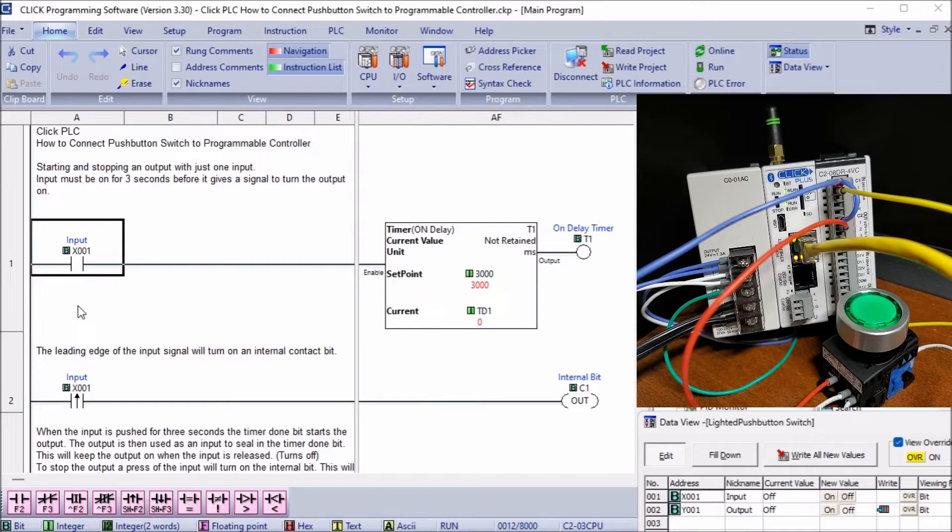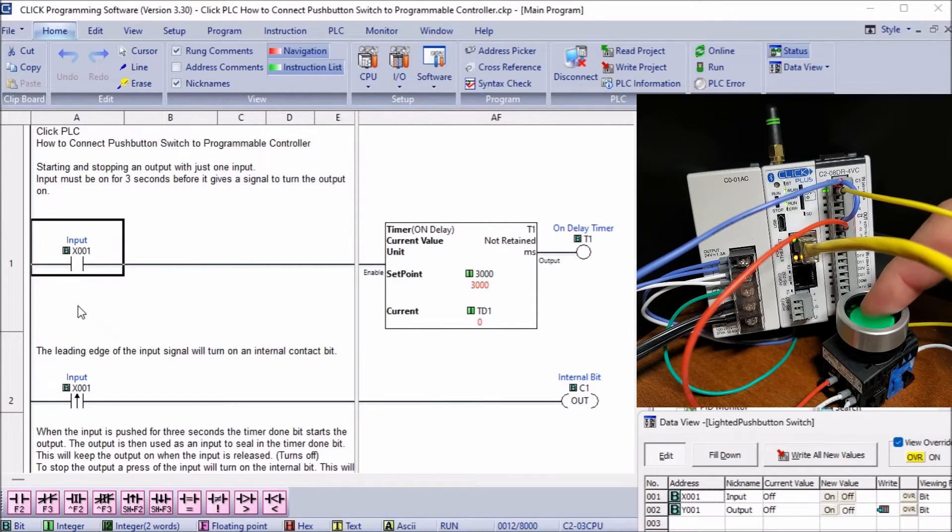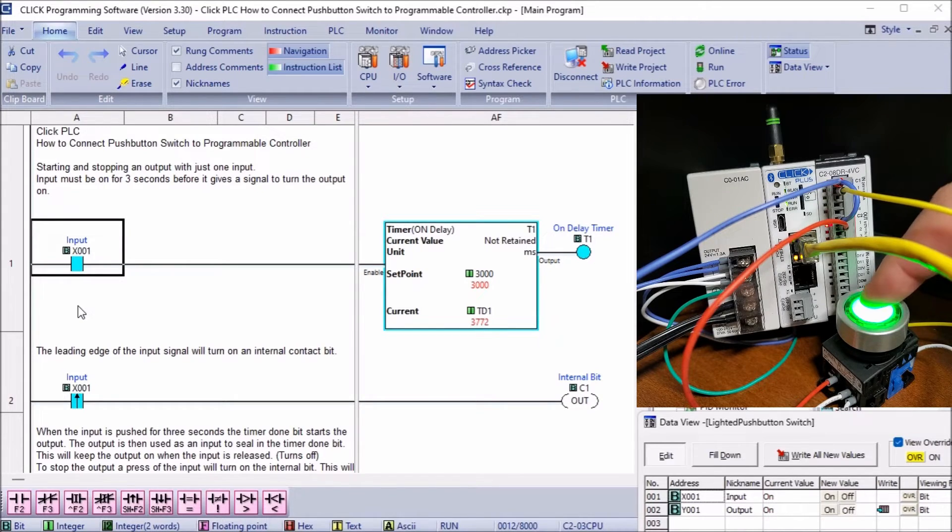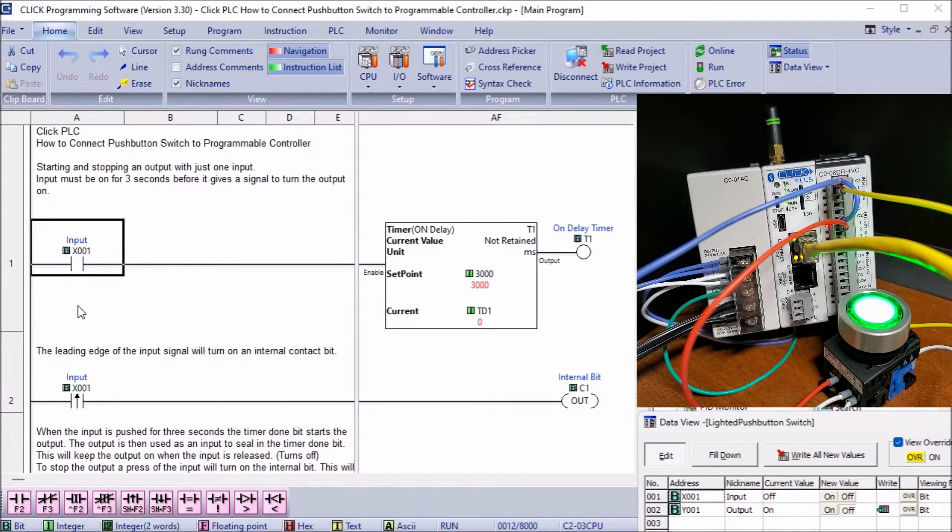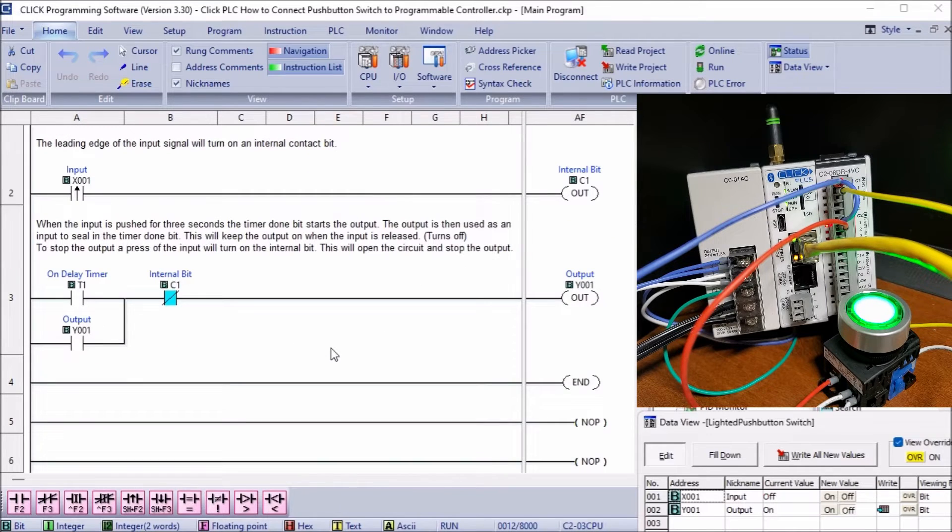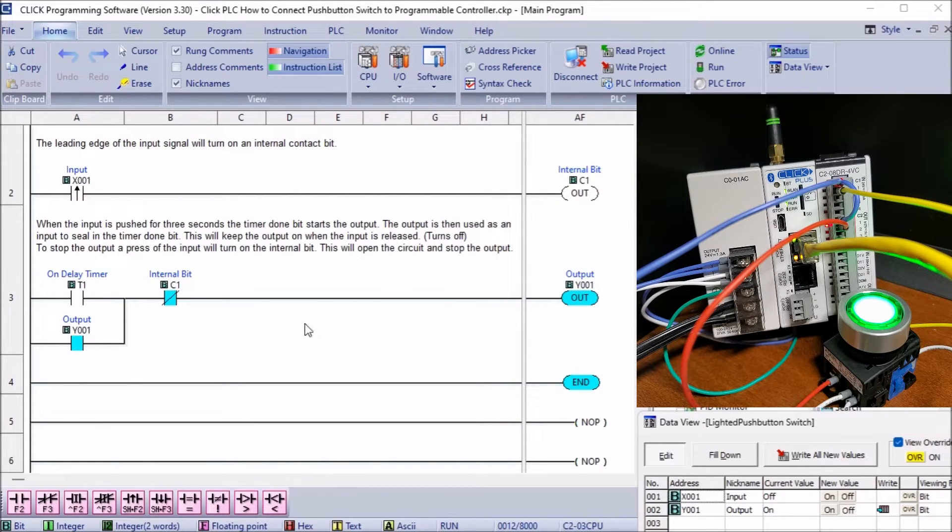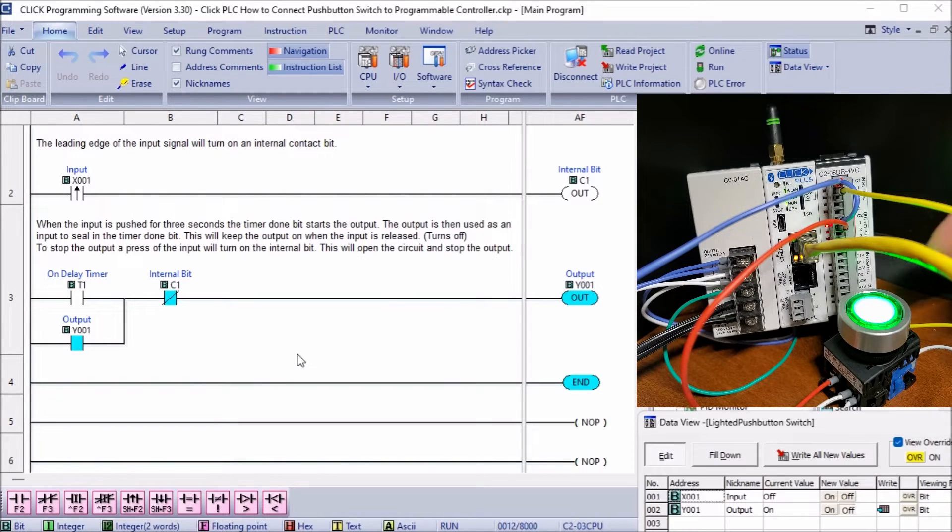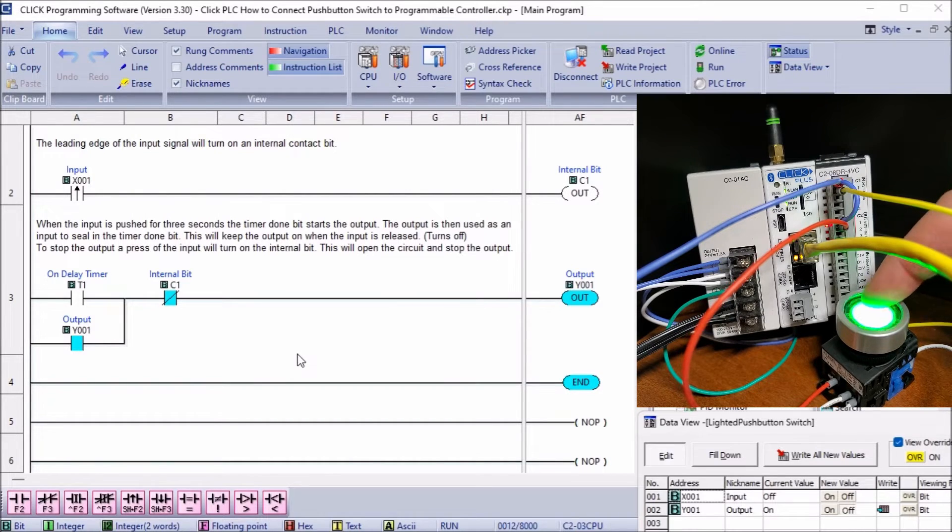Pressing the pushbutton will start our on-delay timer. Once the timer is finished timing, it will turn on the output. The pushbutton can now be released. The output will remain on due to the sealing contact on rung 3. Pressing the pushbutton again will reset the output.